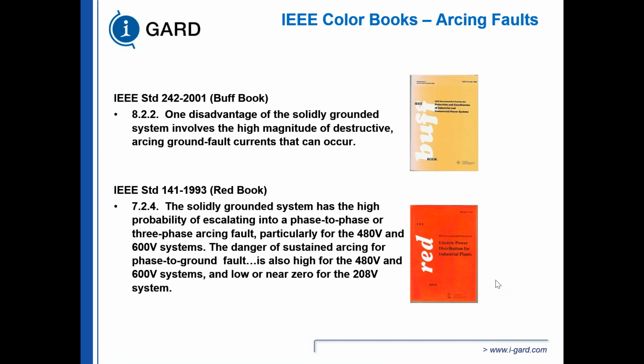Solidly grounded systems have a high probability of having a single phase to ground fault propagate to a phase-to-phase or three-phase fault. And basically what happens is there's so much energy being produced in the single phase to ground fault that we have molten steel, molten copper, and a lot of debris contaminating the insulation. Air is insulation, and if it becomes contaminated, it becomes a better conductor, thereby creating a phase-to-phase or three-phase fault. The solidly grounded system has the highest probability of escalating into a phase-to-phase or three-phase fault, particularly in 480 and 600 volt systems, because your voltage gaps are reduced at 480 and 600 volts.